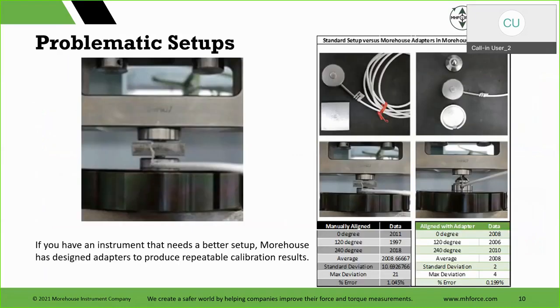This is a headache for everybody. The typical setup is on the left, right? If you're using these, your technicians are going to be crying. I can't get these in from one cal to the next. The alignment, I get this in, I did this calibration. Hey, manager, I did this calibration, and then I went to do it again half an hour later and it's different. Or this thing comes back every six months, and every time it comes back, we're adjusting it for the customer. That's a problematic setup. So this is where adapters come in, and we have solutions for all these setups.